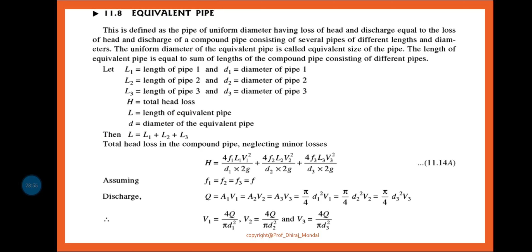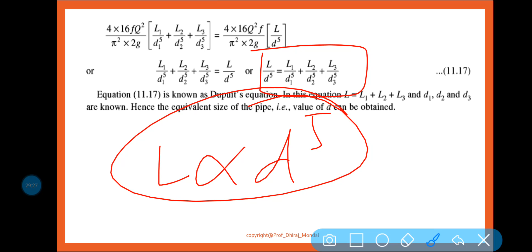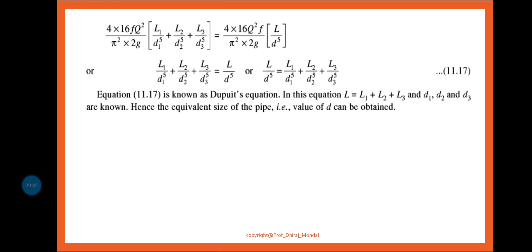To eliminate this part, you have to make it an equivalent pipe, where the losses are already accounted for, and HF is equal to, for the equivalent pipe this is the equation, and for the compound pipe this is the equation. If I equate these two, you will get this formula. So L is proportional to D to the power 5. Okay, so L by D to the power 5, equivalent length by equivalent diameter to the power 5, is equal to L1 by D1 to the power 5 plus L2 by D2 to the power 5 plus L3 by D3 to the power 5. Okay, so this is the end of the video.